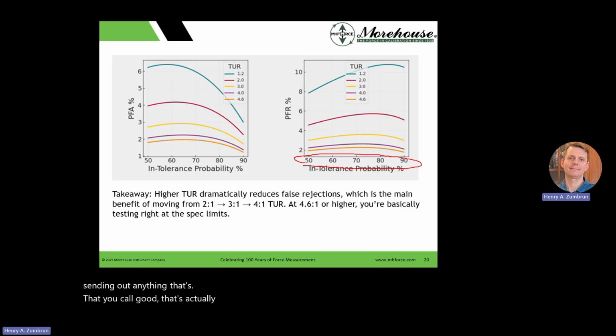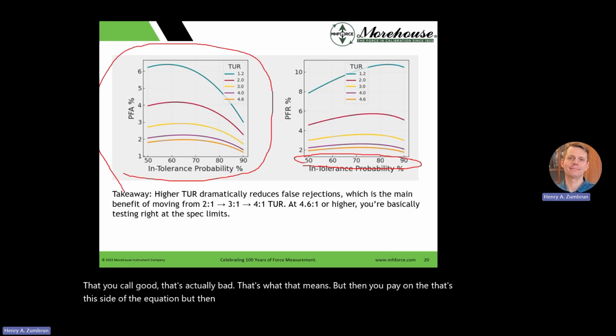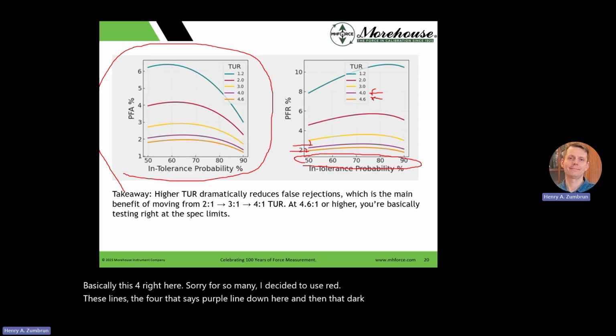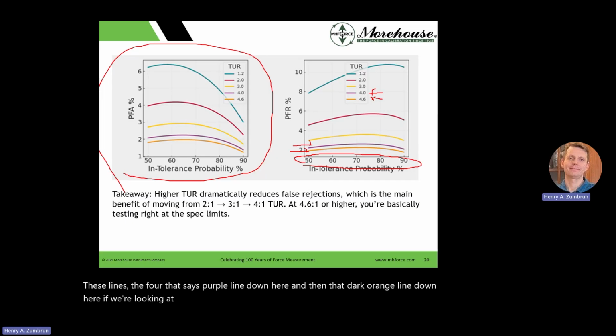That's what that means. But that's this side of the equation, and then you pay on the PFR side of things. So you're rejecting a lot more. You're adjusting things that do not need adjusting. So that's what happens at a measurement capability index of TUR, basically this 4 right here. Sorry for so many, I decided to use red. These lines, the 4, that's that purple line down here, and then that dark orange line down here. If we're looking at measurement capabilities of 4 and 4.6, it becomes really small, PFR approaching 0% at 4.6.